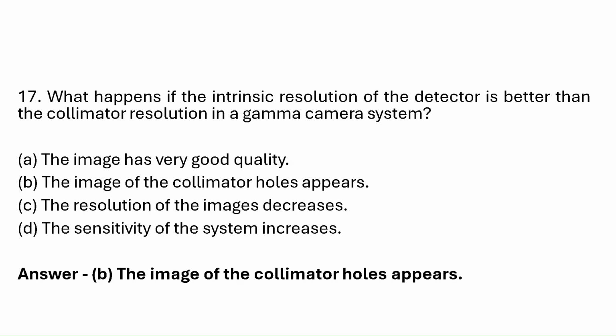If intrinsic resolution is better than collimator resolution, the overall resolution depends upon these two, intrinsic plus collimator. If intrinsic is better than the collimator, then what you will see is the image of the collimator holes appearing on your screen.